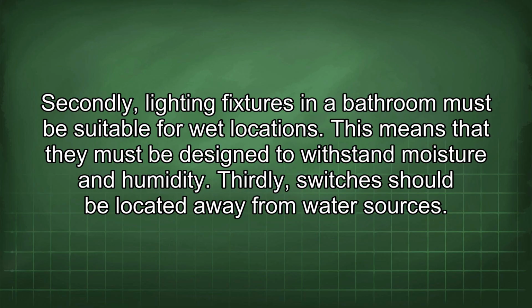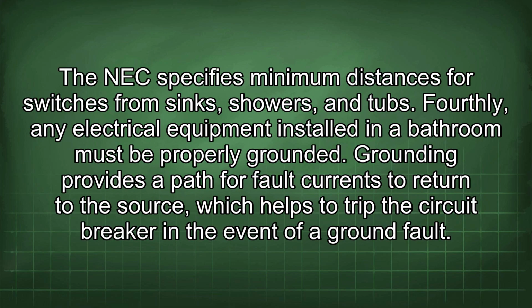Secondly, lighting fixtures in a bathroom must be suitable for wet locations. This means that they must be designed to withstand moisture and humidity. Thirdly, switches should be located away from water sources. The NEC specifies minimum distances for switches from sinks, showers, and tubs. Fourthly, any electrical equipment installed in a bathroom must be properly grounded. Grounding provides a path for fault currents to return to the source, which helps to trip the circuit breaker in the event of a ground fault.